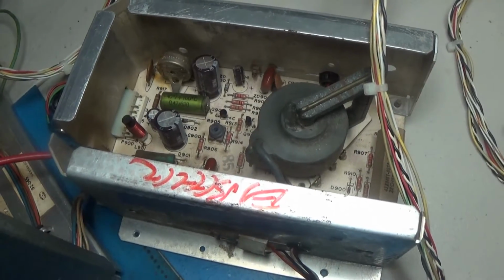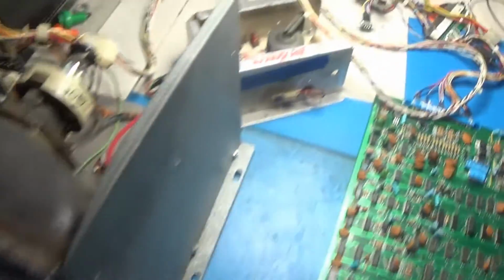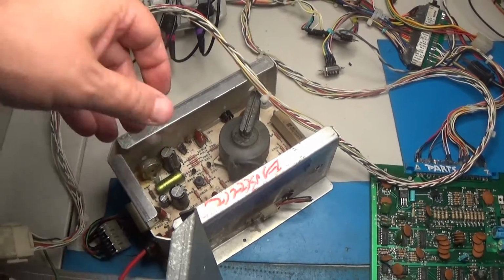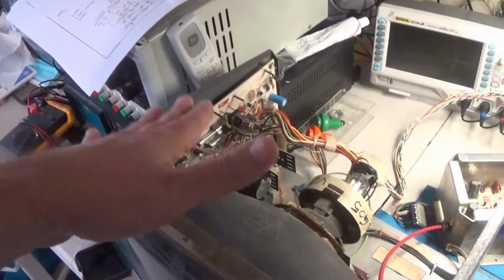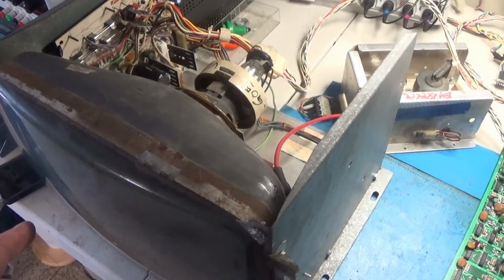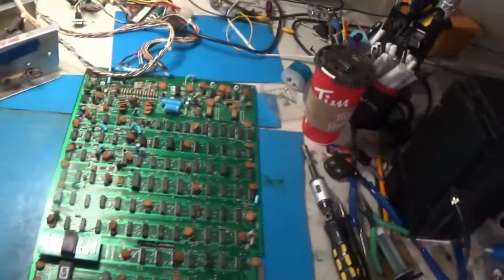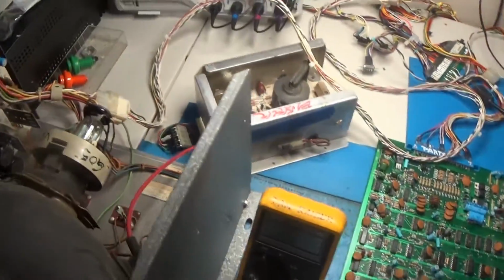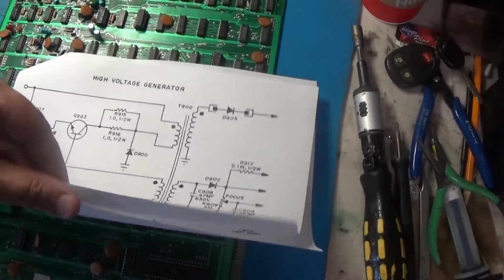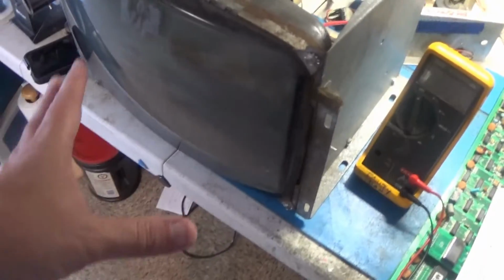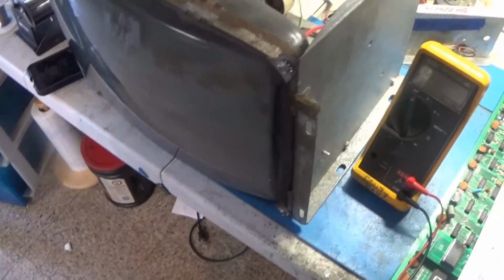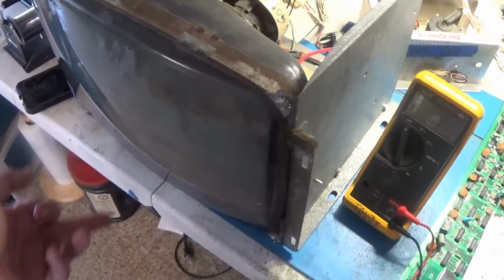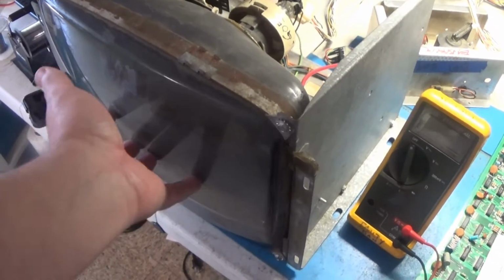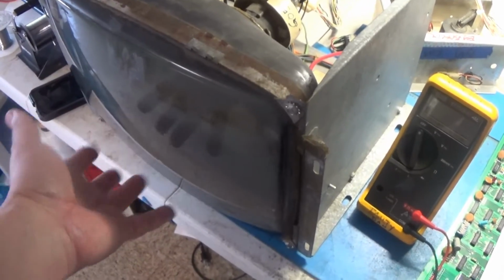This one has been capped, but you saw when I had this thing running, the high voltage control down there doesn't do anything, and the brightness control doesn't do anything. I've already verified that the deflection board's good, so that's not an issue. Now let's grab this and take a look at this schematic here. The Z amp, which is the brightness amp on here, can take the beam from 0 to full brightness, and right now it's just stuck on full brightness. There's no Z amplifier at all on this thing.